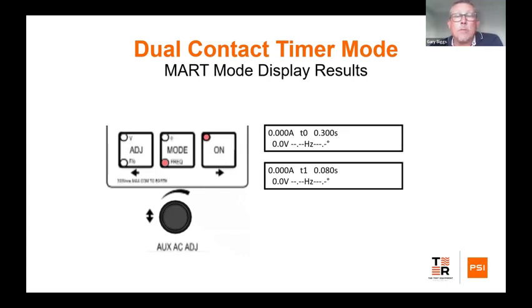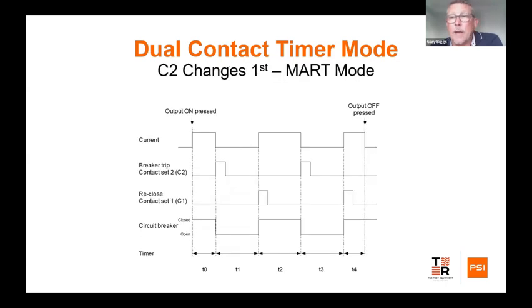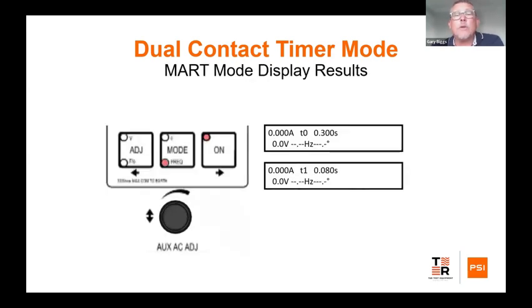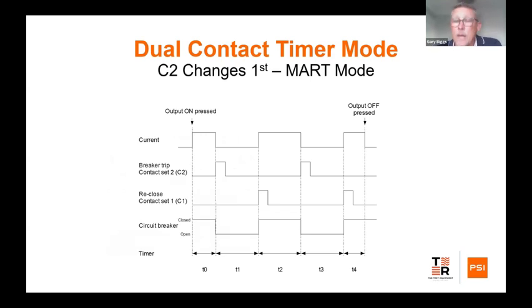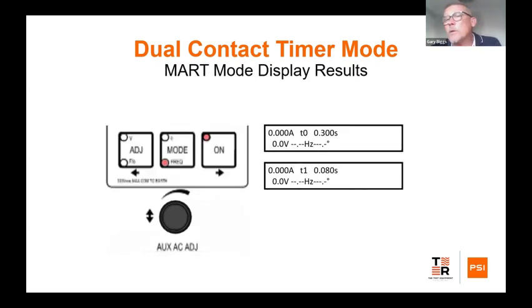And as I said, the MART mode results, we can download them, and this is what they would look like if we download and graph them. But we can also view them on the instrument itself using the auxiliary adjustment, and we can go through and it will say T0, T1, T2, T3. So each time, each operation of the relay, we can see how long it took to operate. And that is the same information that we're seeing graphed there. So we can either graph it, or if we wanted to look at the information on site, we can also view that information on site.